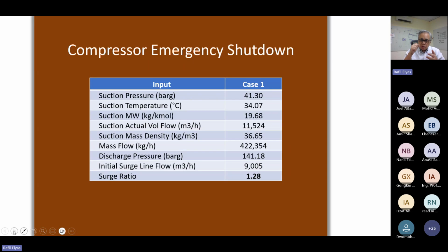And even though you have an anti-surge valve, because the power cuts off very quickly, sometimes the valve can't open enough to give you enough CV to have the flow come back. So you have a backup valve or a fast stop valve, a valve that you can actuate very quickly, just open it fully in a short period of time to allow the recycle flow to go back. So this is an example for a compressor shutdown.